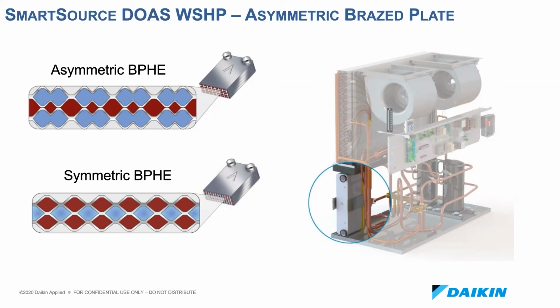The older brazed plate designs required a 60 mesh strainer to filter debris from the water. The new asymmetric design requires a 20 mesh strainer, which is the same strainer that we already offer as an accessory in our hose kits for the units with the coax style heat exchangers.